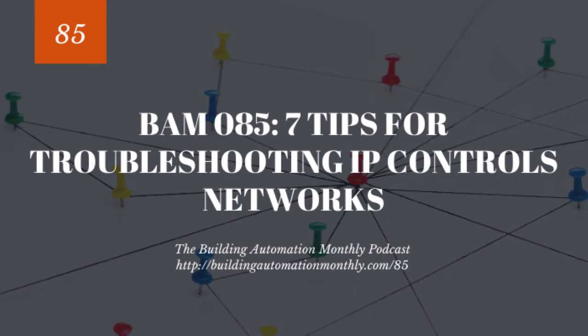I wanted to create some tips here that had kind of a memory to them. You could remember these because they're a little funny, a little off in left field, I guess. So get physical. What I mean by that is so often I'll talk with folks and they're like, help me troubleshoot this VFD, or help me troubleshoot why this relay is not turning on. Help me troubleshoot this, help me troubleshoot that. And oftentimes the answer is the physical wiring, the power. Is it connected to the right device?